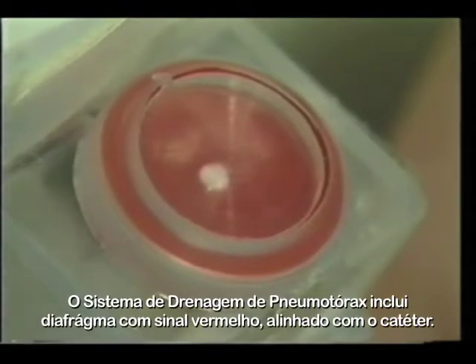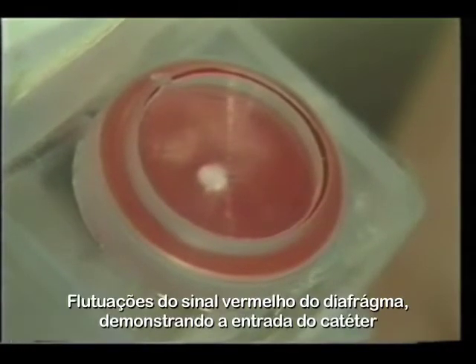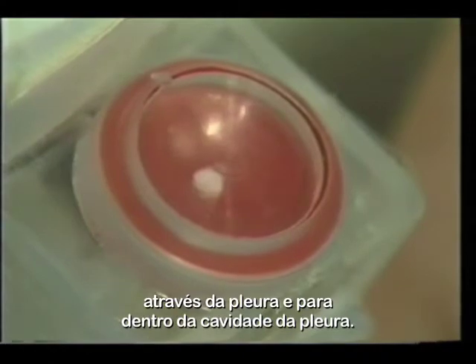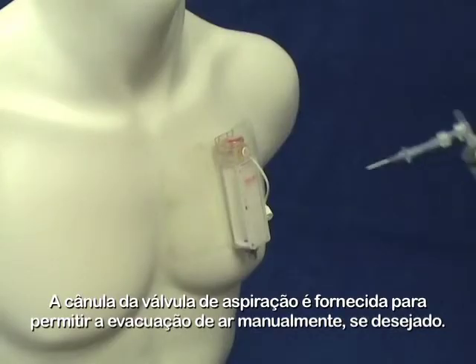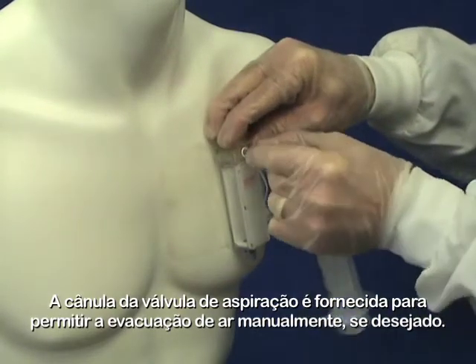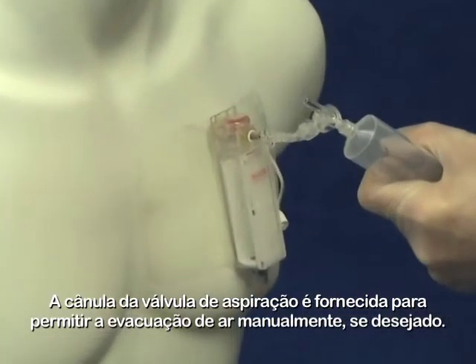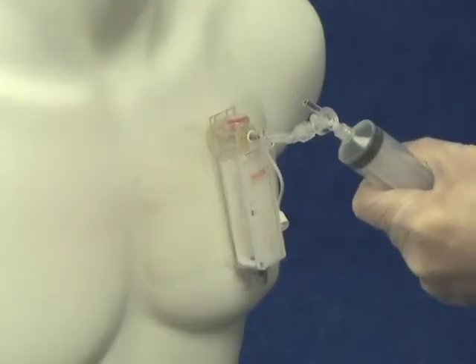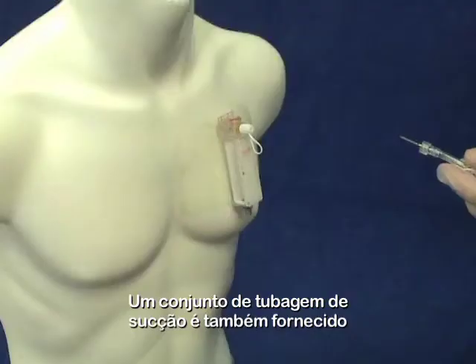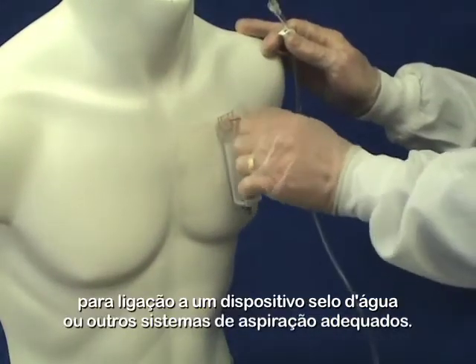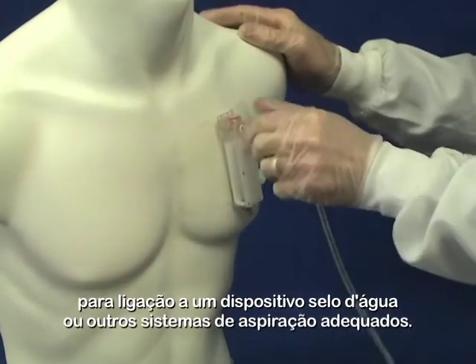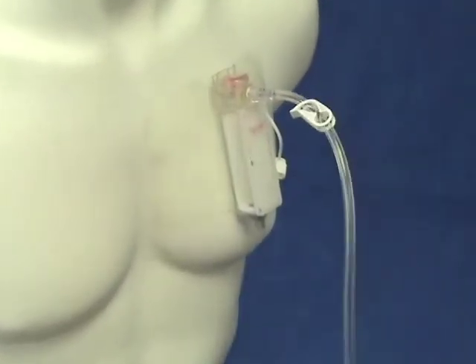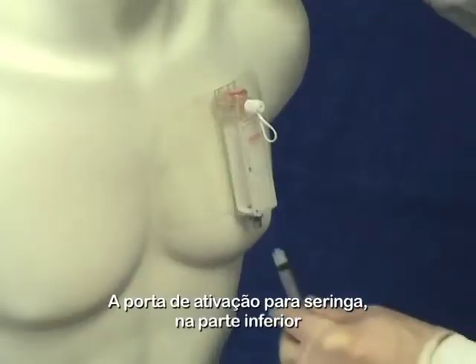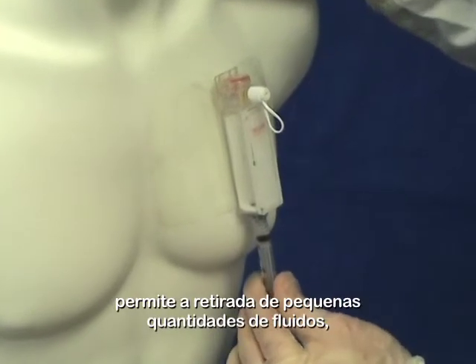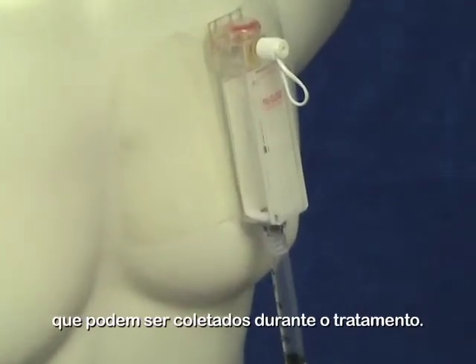The thoracic vent includes a red signal diaphragm in line with the catheter. Fluctuations of the red signal diaphragm demonstrate entry of the catheter through the pleura and into the pleural cavity. A valved aspiration cannula is provided to allow manual air evacuation if desired. A suction tubing set is also provided for attachment to a water seal device or other suitable suction systems. The syringe-activated port at the bottom of the vent allows for the aspiration of small amounts of fluid that may collect during therapy.